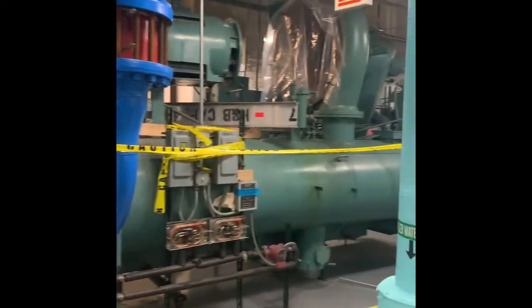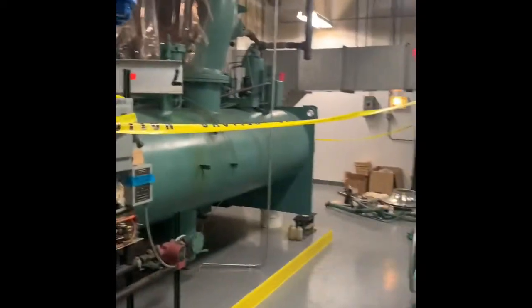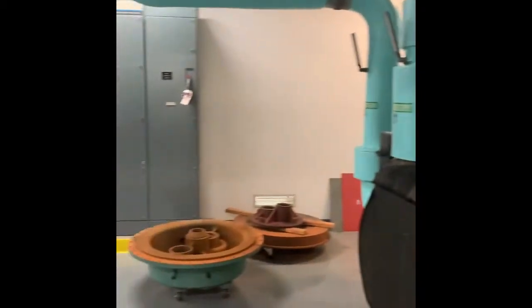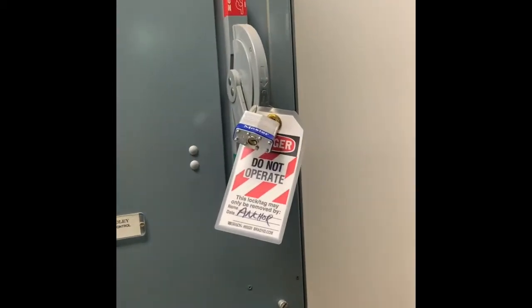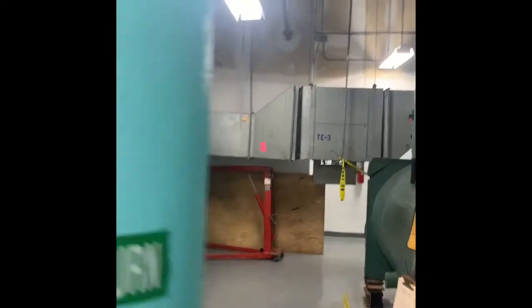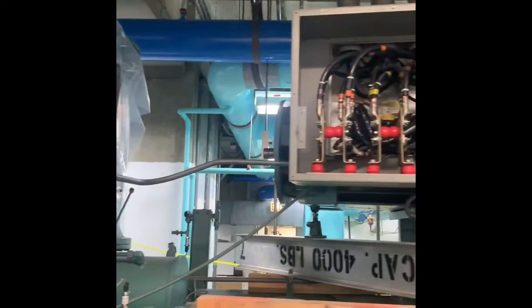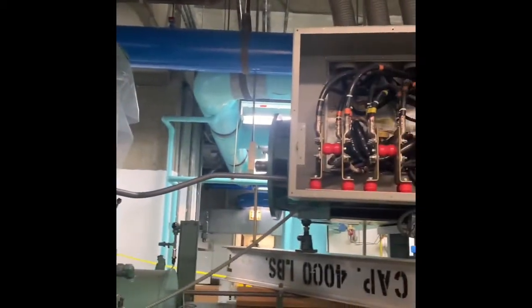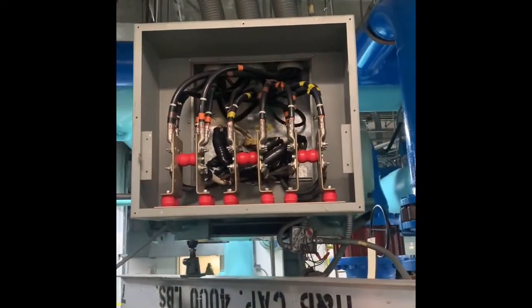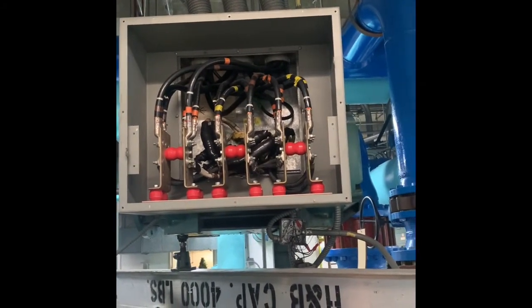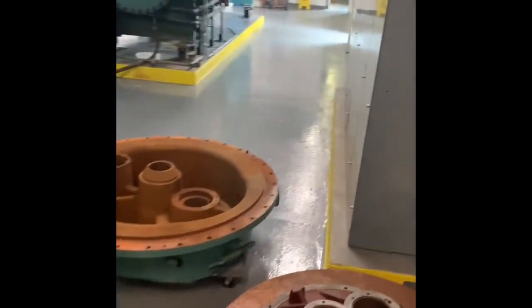I'm doing a little work on this chiller here. Got it all tore apart. Here's the starter, and you'll see there is lockout tagout on this motor control. We don't want anybody accidentally turning on the power when the motor has been removed. The motor's gone, and there's the open connections to it. So we definitely don't want anybody accidentally harming themselves.